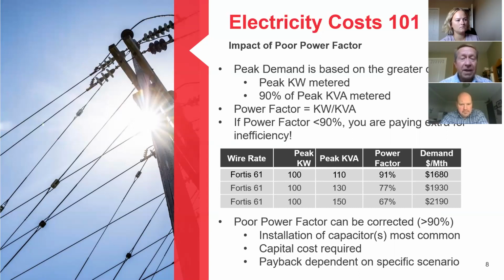So the table that I show there indicates the monthly cost for the demand portion of the Fortis wire's rate 61 for a power factor, first of all, that's slightly above 90% and then decreasing. What's important to note here is that in all three cases, the kilowatt peak is still 100, and that's the real work being done in the operation. That remains the same, but because the power factor is dropping below 90%, your demand charge on the wire's rate increases because the measured kVA has increased.